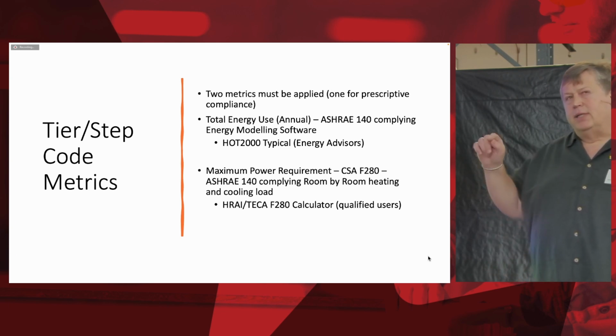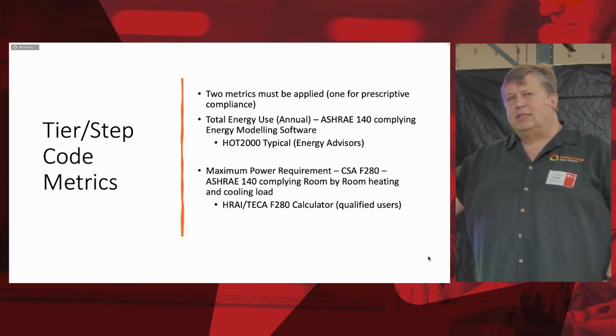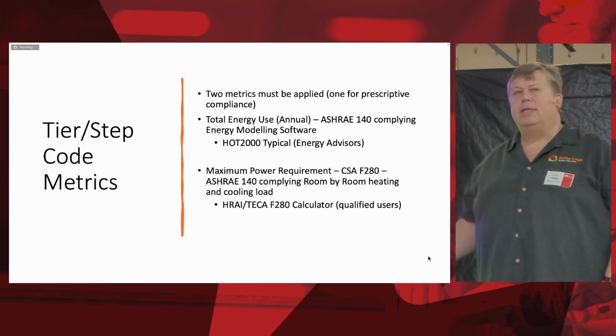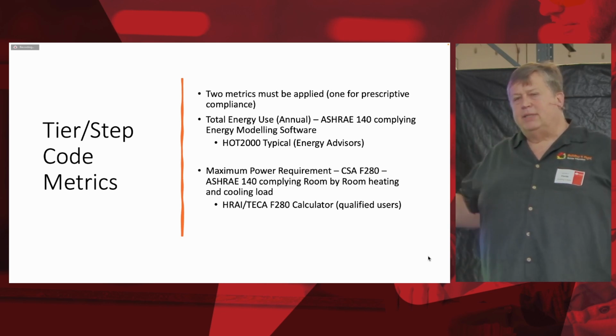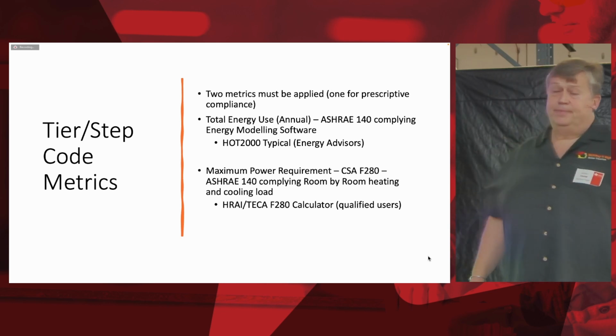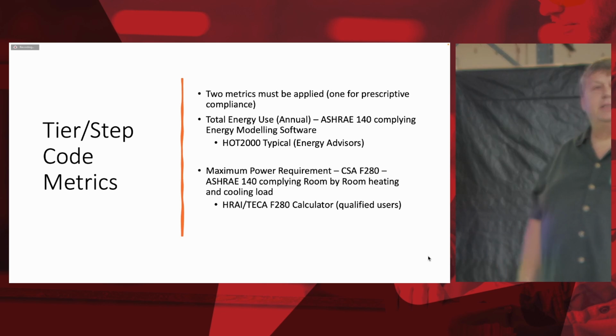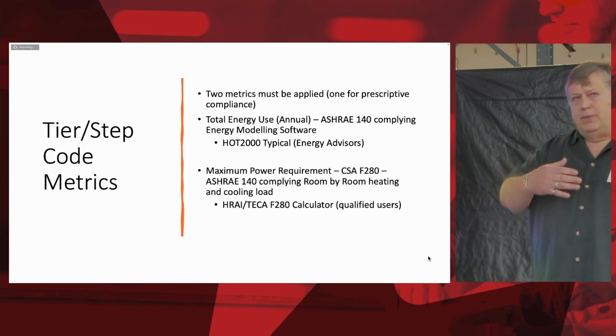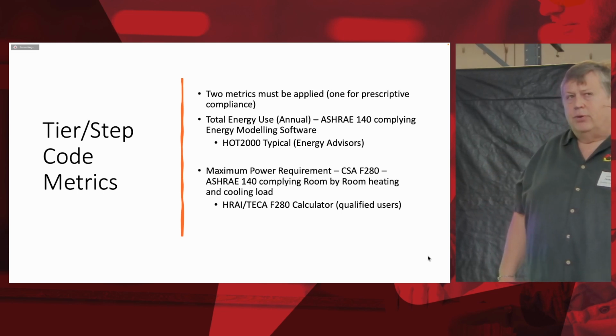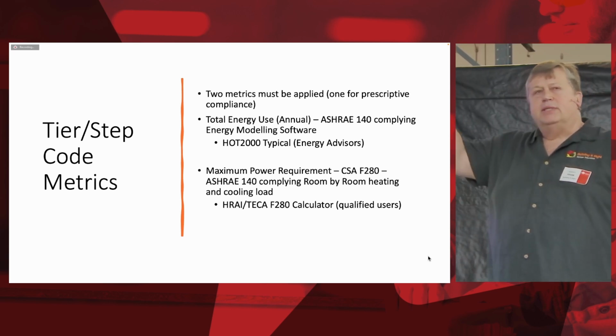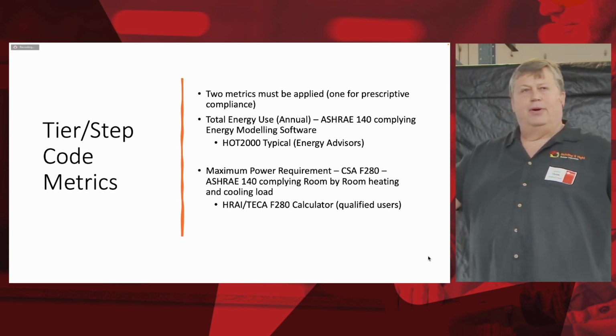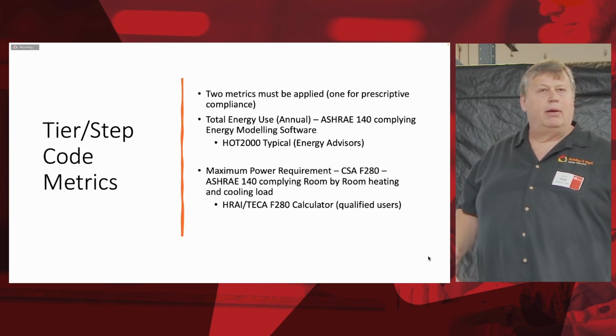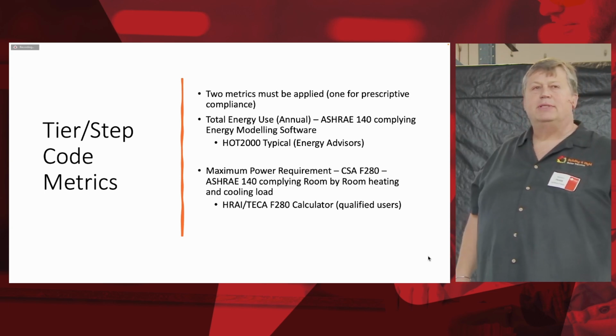The power calculation, the room by room calculation, tells you exactly how many BTU you need to effectively provide in heating and/or cooling on a room by room basis and on a total building basis. Now you know how big that thing needs to be, how many BTU, how many tons, whatever reference you want to use for those mechanical devices. And then you still do an energy model calculation that gives you the energy total, because that's what we're using as a metric to say it's better than it was before. It is that 80% better, or better than 80%, than the reference house.